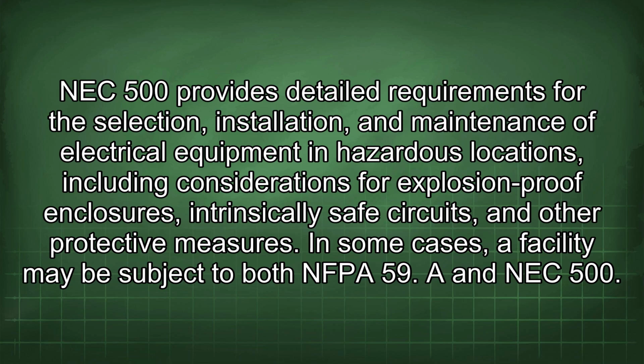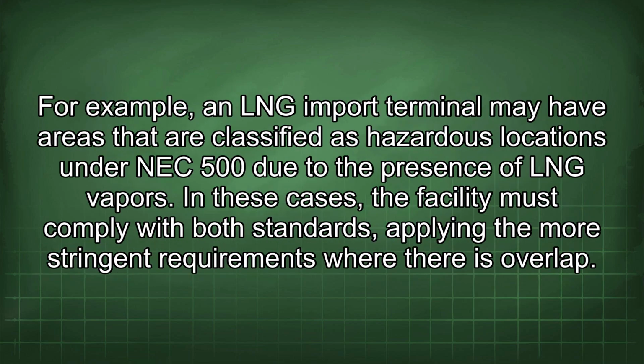In some cases, a facility may be subject to both NFPA 59 and NEC 500. For example, an LNG import terminal may have areas that are classified as hazardous locations under NEC 500 due to the presence of LNG vapors. In these cases, the facility must comply with both standards, applying the more stringent requirements where there is overlap.